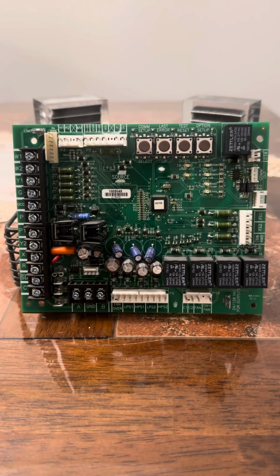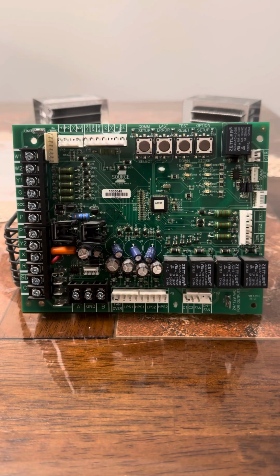This is the Simplicity board, the York Johnson Controls Simplicity board that they used to use on their ducted systems equipment before they came out with the smart equipment, with the smart board with a little screen on the side. The bigger two-stage boards have the 4 buttons on it, and then you've got the smaller board that's only got the 3 buttons on it, but they're very similar to each other in terms of the fault codes. Right now we're just going to be discussing the 9 flash code, which stands for ignition control lockout.